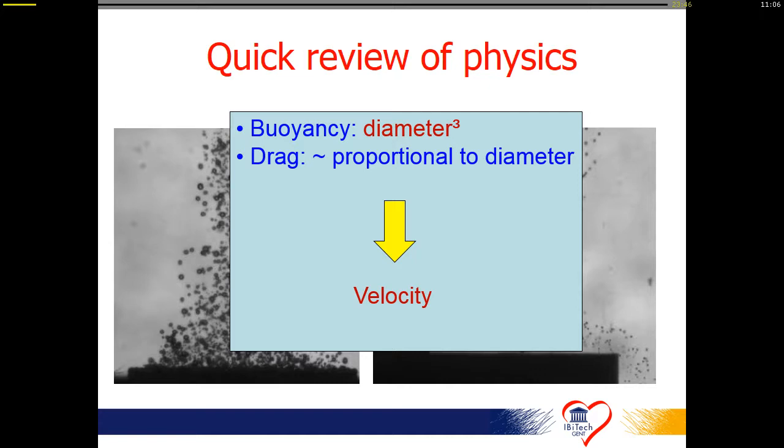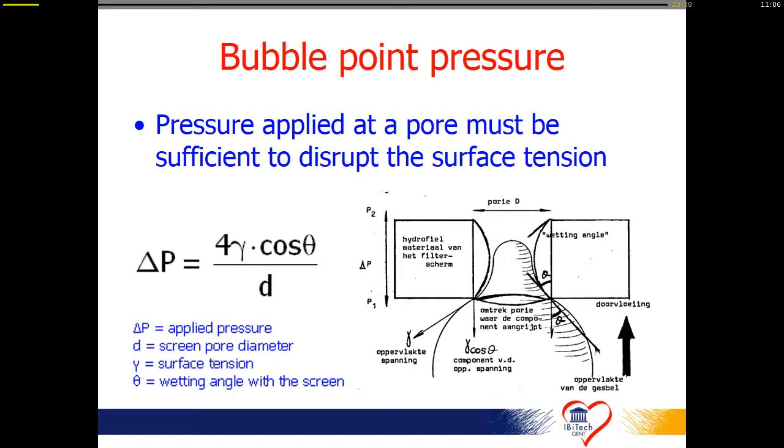And in opposition to what still a lot of people believe, there is no absolute filter available on the market for gaseous microemboli. So what's the bubble point of it? And that's important to also keep in mind. It's highly depending on the pore size, as you can see here. If you would have a 40 micron filter or a 20 micron filter, based on this formula, you can see this will increase the resistance to a gas bubble to go through this filter screen.